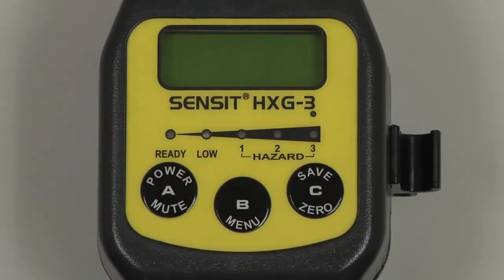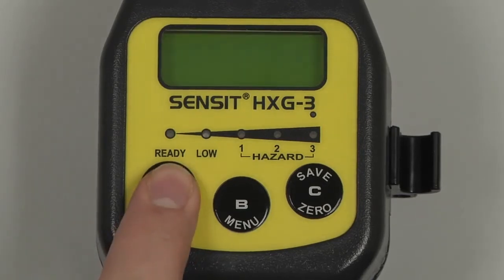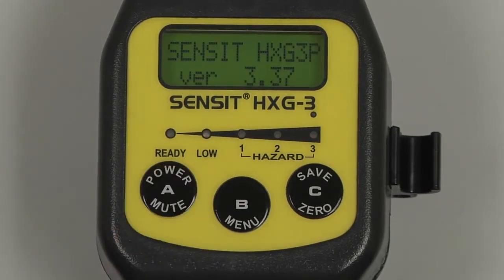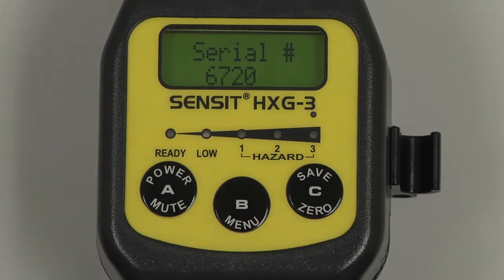To begin, power on the instrument by pressing and holding the A button. The model type and hardware version number will be displayed, followed by a system check. The date and time will be displayed, the gas type, the serial number, and finally a brief warm-up. After the warm-up, the instrument will auto-zero, and the screen will advance to the working display.